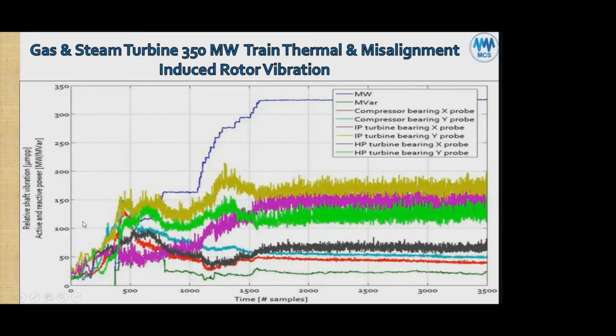there's quite a bit of variation. Here's the variation, for example. We have the IP turbine Y probe dropping down to roughly 110, and then gradually growing up to 210 microns. That's a lot of microns, basically 110 to 210. That's about 4 mils, since 4 by 25 is 100 microns. So about 4 mils vibration variation. However, gradually it starts to settle down and it's becoming smoother here. Not the best, but smoother. In proportion to the size of this machine, if we say 350 megawatt, it's not acceptable.